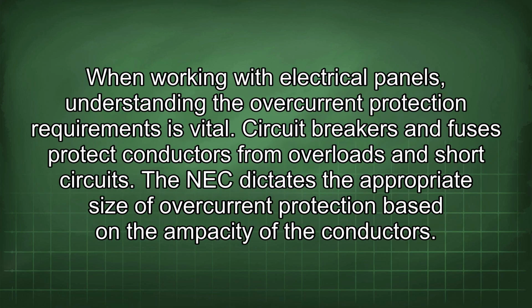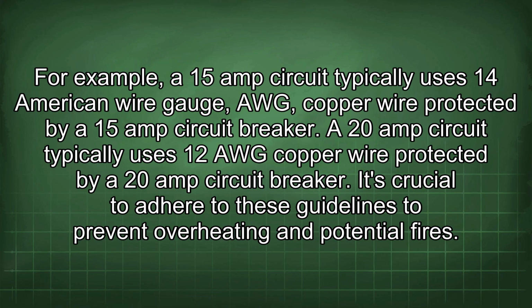When working with electrical panels, understanding the overcurrent protection requirements is vital. Circuit breakers and fuses protect conductors from overloads and short circuits. The NEC dictates the appropriate size of overcurrent protection based on the ampacity of the conductors. For example, a 15 amp circuit typically uses 14 American wire gauge (AWG) copper wire protected by a 15 amp circuit breaker. A 20 amp circuit typically uses 12 AWG copper wire protected by a 20 amp circuit breaker. It's crucial to adhere to these guidelines to prevent overheating and potential fires.